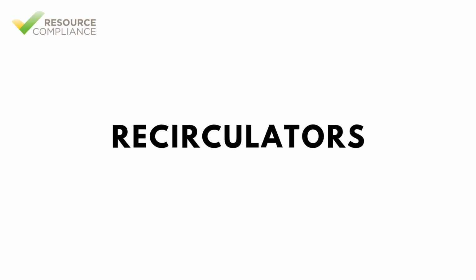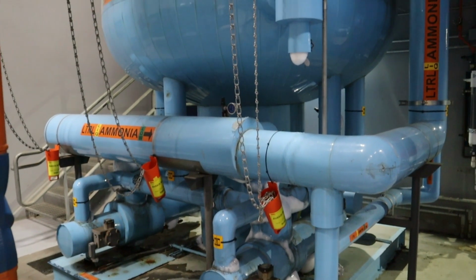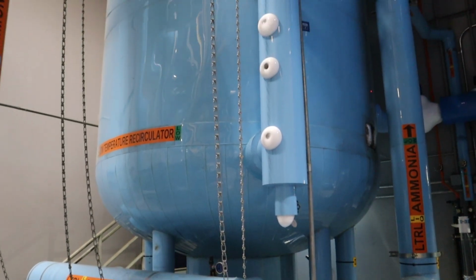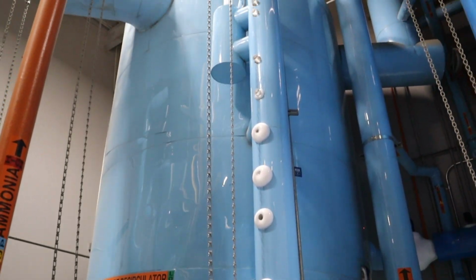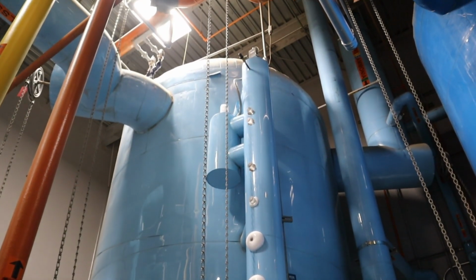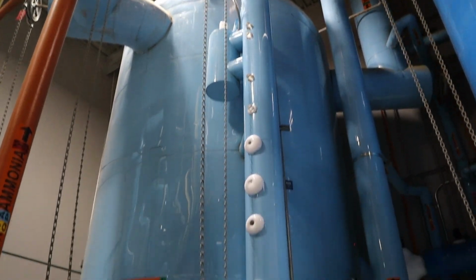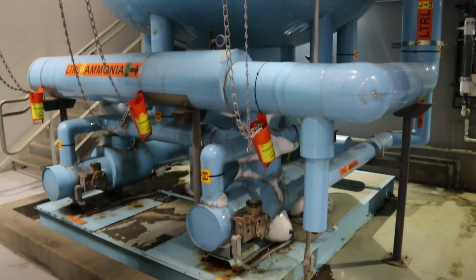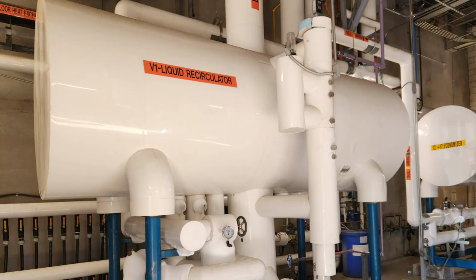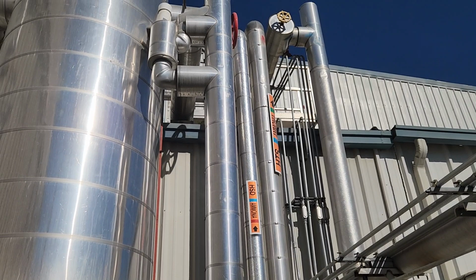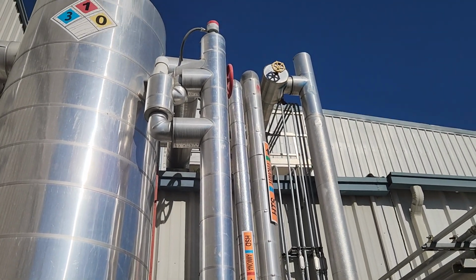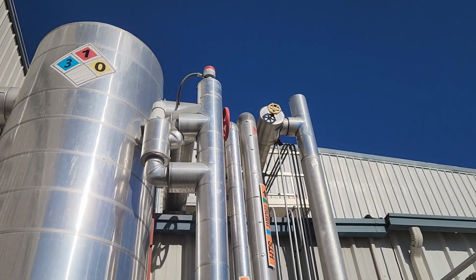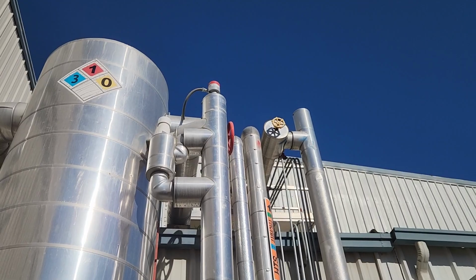A recirculator is a vessel designed to supply liquid refrigerant to the evaporators at a controlled rate while collecting and returning excess liquid refrigerant for reuse. It is primarily used in large industrial refrigeration systems, particularly those using ammonia as the refrigerant. The recirculator provides efficient refrigerant distribution, ensures the entire evaporator tube surface is wetted, and allows the system to use less refrigerant than gravity-fed or flooded systems.